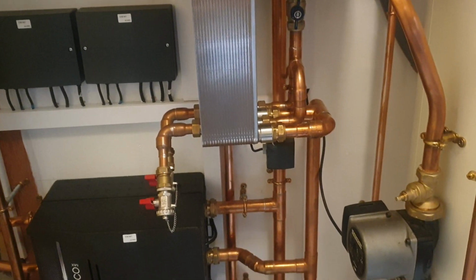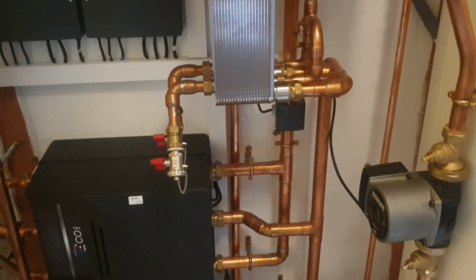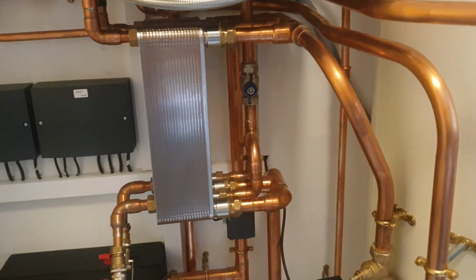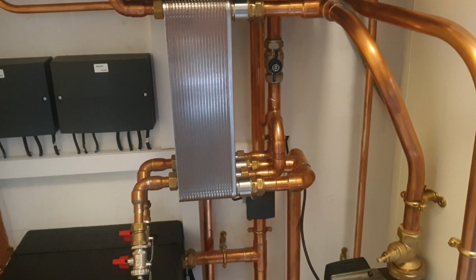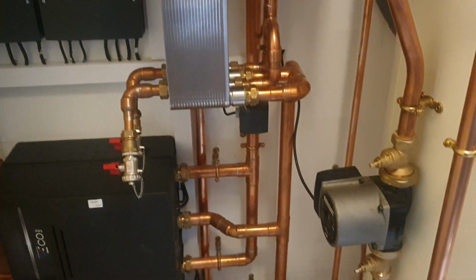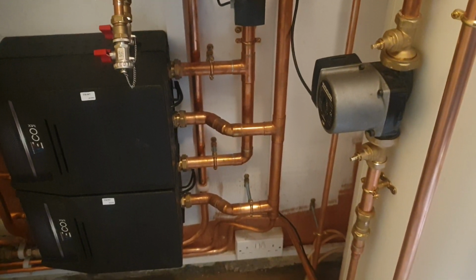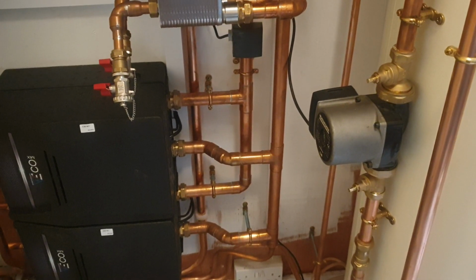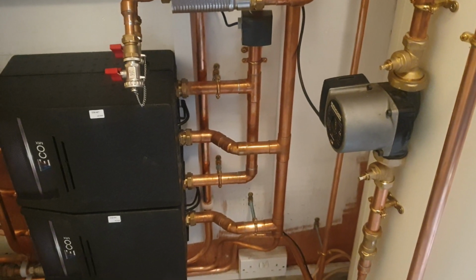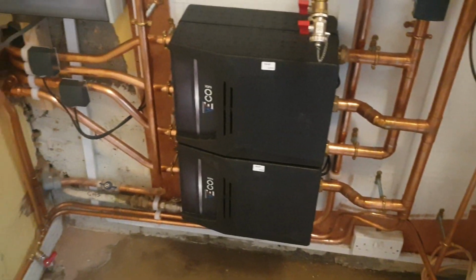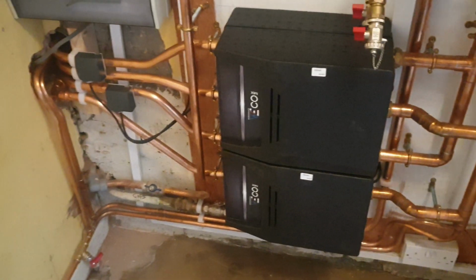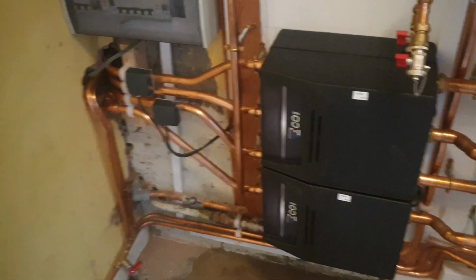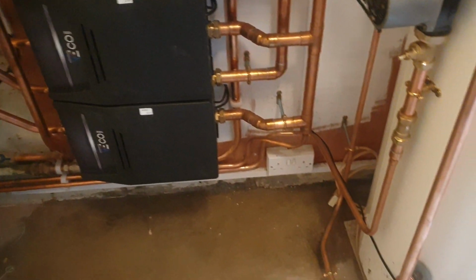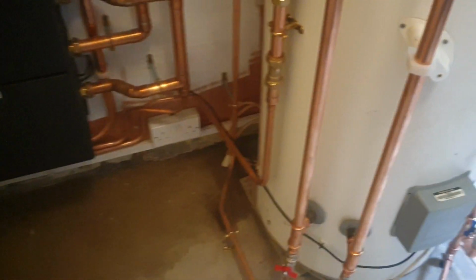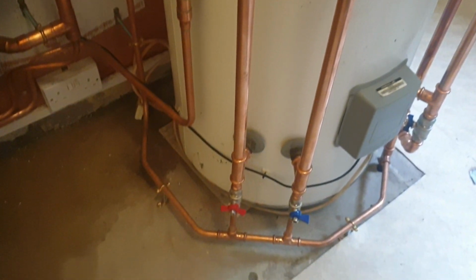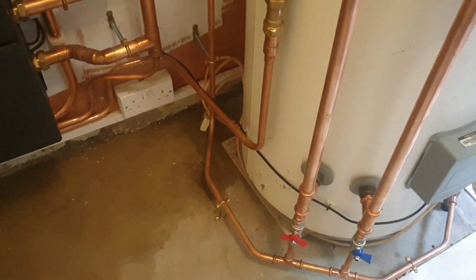And down here again, so twin plates for underfloor heating, just trying to make sure we get the lowest pressure loss through there possible. 28mm common header there into those, and then through the 2 mixers, 22mm circuits out for those. The underfloor manifold is just the other side of that wall. So the 2 radiator circuit comes down 22 down to 15, and it's run off the bottom there.